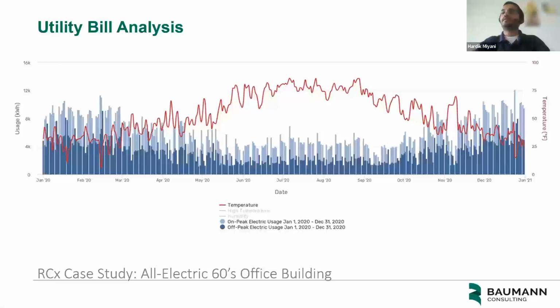This graph shows the daily electric consumption correlated with the daily average ambient temperature for the year 2020. The line in red represents the daily average ambient temperature, while the blue represents the overall energy usage for the entire year. As we can see from the graph, when the ambient temperature goes below 50°F, the electric usage goes up. We can see that for the months of January, February, and late December, which is expected since it is an all electric building. So this is one way to help us determine that a considerable amount of energy is being spent on heating in this building. This is the first step for us to identify where the major energy is being spent for this type of building.